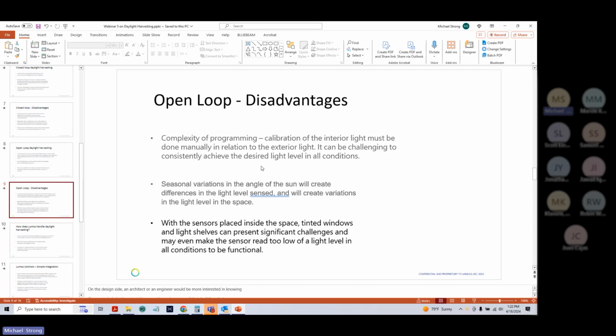Now, where open loop is great is places like a warehouse where it has a lot of skylights. And what we would do is we would place a photo sensor at the top end of where the lights are. We would point the photo sensor directly at the skylights, and we put this above the lights naturally so that no artificial lights, other than perhaps some small reflectance, but if you put it on top of the light, the chances for reflectance are slim. And we point it directly at the skylight. Anyways, seasonal variations in the angle of the sun will create differences in light level sense.